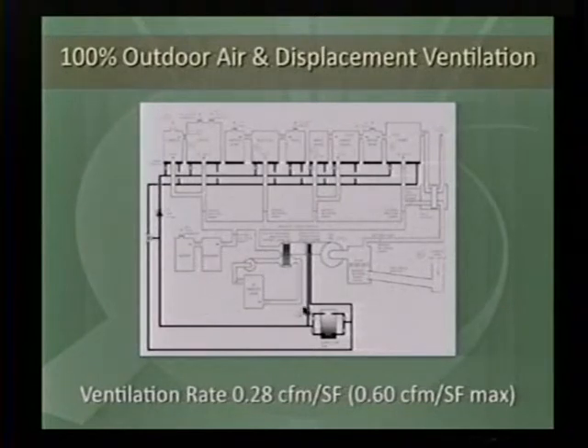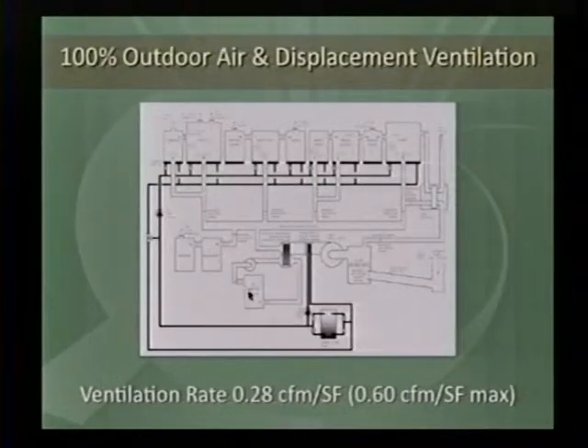The other issue here, we've got a 40 kW PV system, and so we've got a lot of waste heat coming off the inverters. And we have a single coil in our air handling unit. We need to do some reheat on the air system in the summer. So we thought we would put in a fan to go through the inverter room and a heat pipe to do basically a little bit of reheat on the air going into the building from the heat pipe.